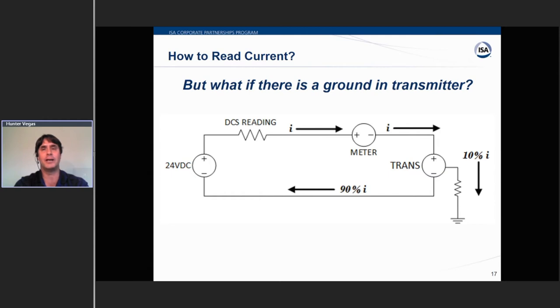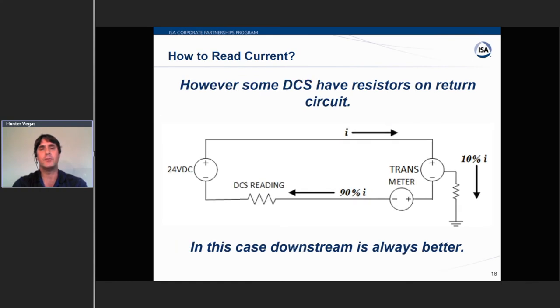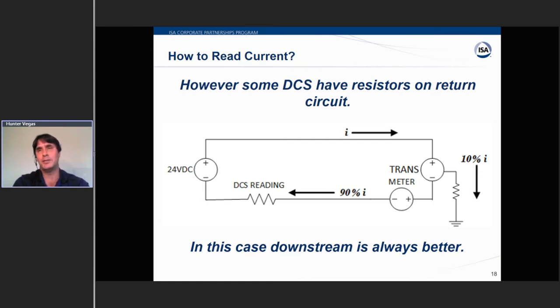If you were upstream, you'd see 100% going to the transmitter but the transmitter giving a different number, and you'd start investigating. The key is to understand how your DCS measures the signal — some DCS systems like Emerson Delta V read the outgoing signal, others read the return signal. Ideally you want to be on the same side as the DCS so your meter and DCS readings match. It's worth understanding how your analog cards work to ensure matched readings.